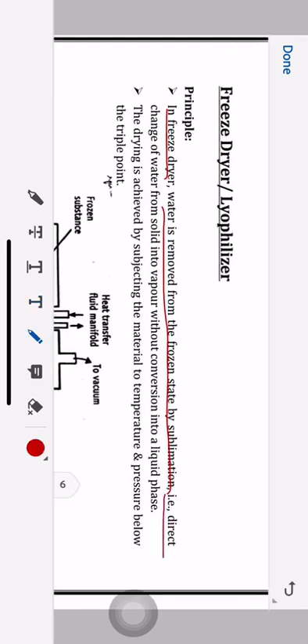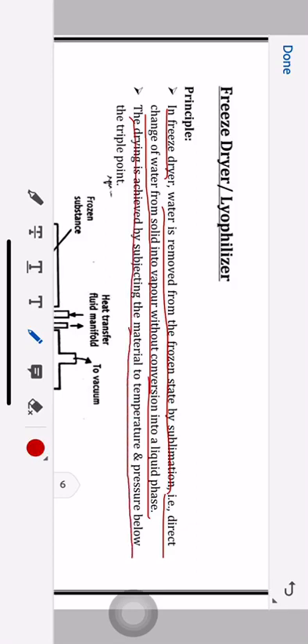The same principle is applied in the freeze dryer. First, you have to freeze your product — convert it into solid form, meaning all the water is converted into solid. Then that water is converted directly into vapor without letting it convert into liquid phase. That is sublimation, and this is how the freeze dryer works. The drying is achieved by subjecting the material to temperature and pressure below the triple point.